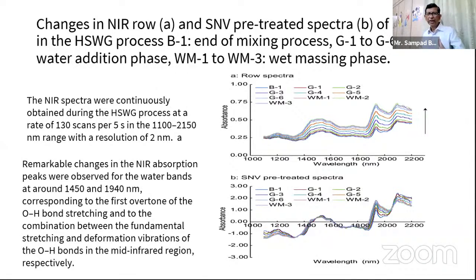And you might have seen that there are two spectra, but in IR as well as NIR, MIR, and to some extent Raman, you have to give the spectra a treatment to eliminate many of the parameters and address the dimensionality, and do some kind of derivatization. SNV is a standard normal variate pre-treated spectra. That removes a lot of noise and a lot of undue, uncorrelated, pseudo correlations. That's why you always have to use NIR with additional treatment, and that's why the chemometrician comes in every time for NIR spectra.